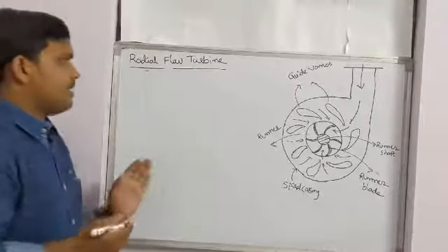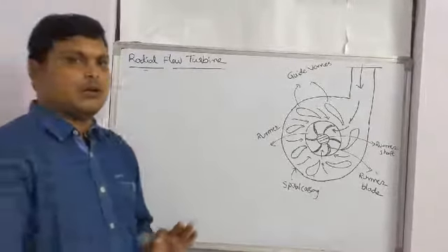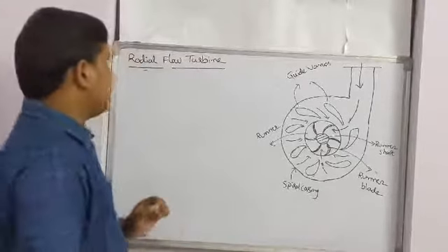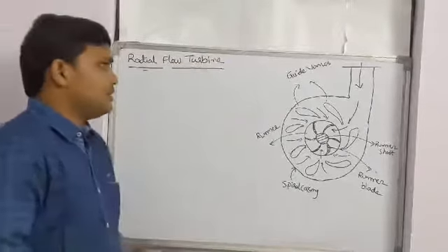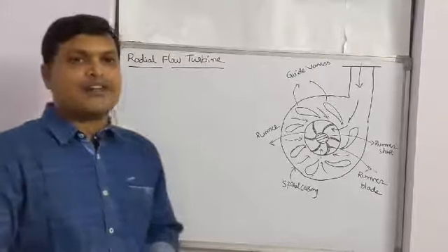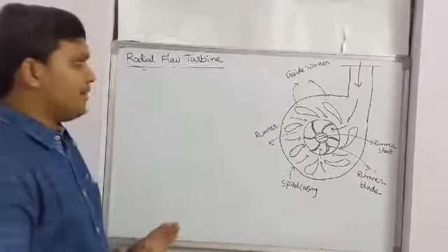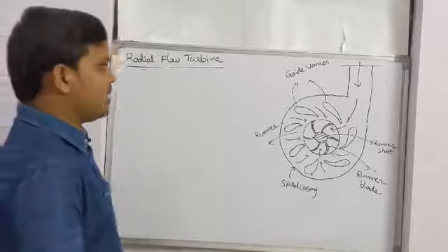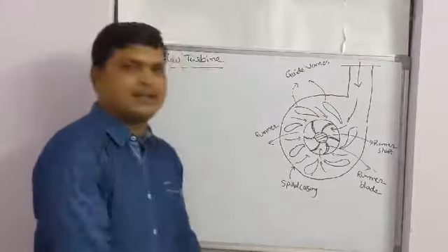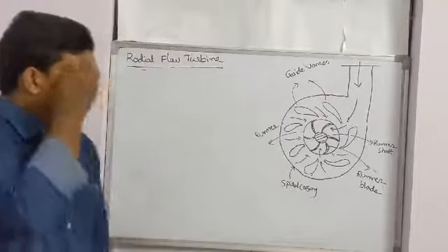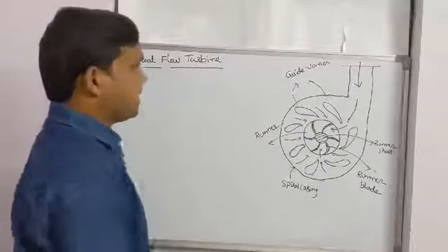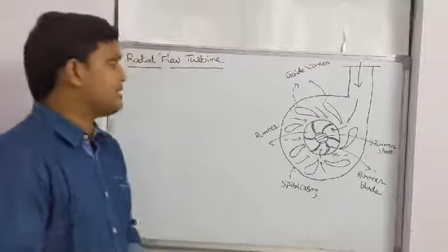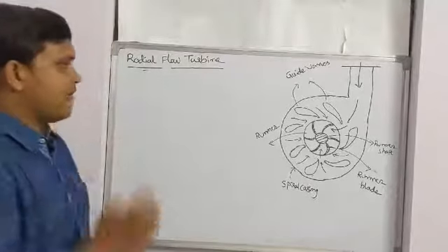Coming to the Francis turbine, the old Francis turbine is a purely radial flow turbine. But the modern Francis is a mixed flow turbine, meaning the water enters the runner blades radially and leaves the runner axially. That is called mixed flow. In the previous class we discussed the mixed flow turbine and the Francis turbine.